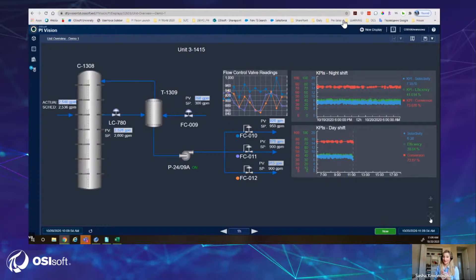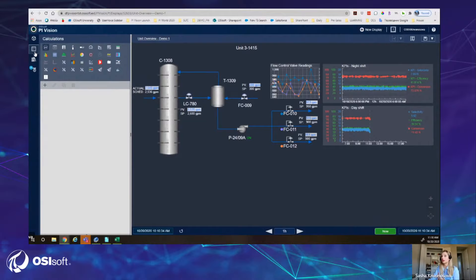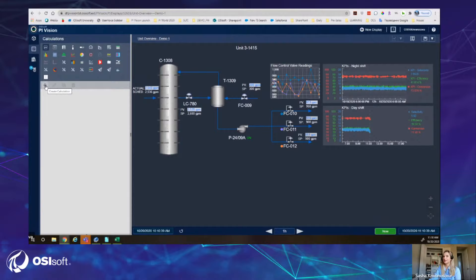Another great capability we're introducing is native calculations on the PI Vision side. We have this process overview with a pump that is not instrumented with a flow meter. However, we have downstream flow control valves that have flow meter measurements, so we can simply calculate as a sum what flow comes from the pump using PI Vision calculations. There's a new tab on the left-hand side to create new calculations or view ones already created.